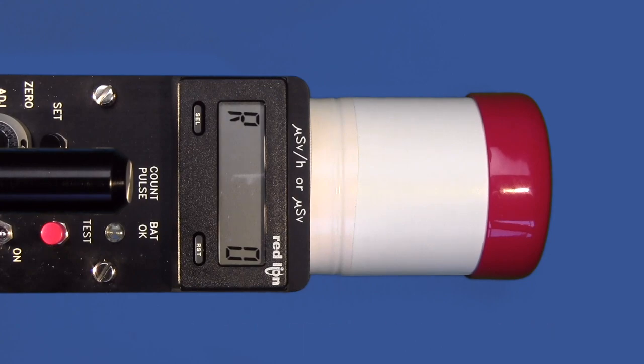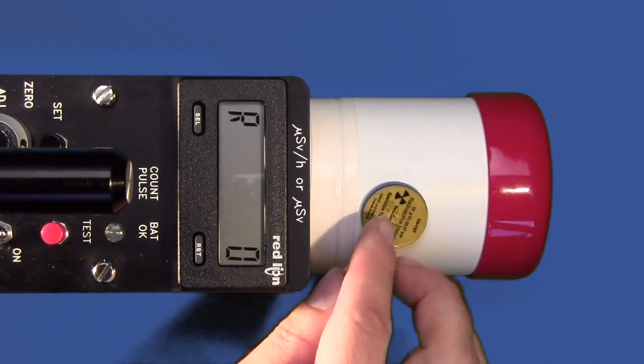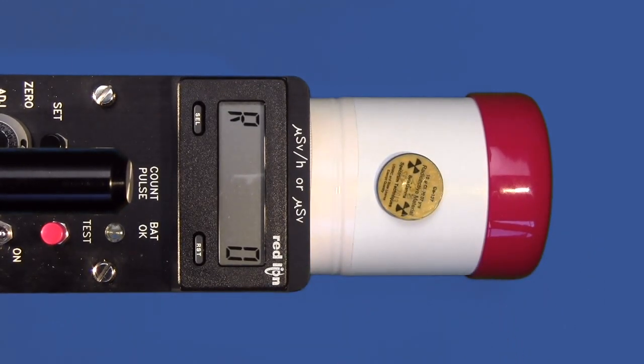In rate mode, I will place the source on top of the air chamber. After a few moments, we see the dose rate is a little under 100 micro-sieverts per hour.